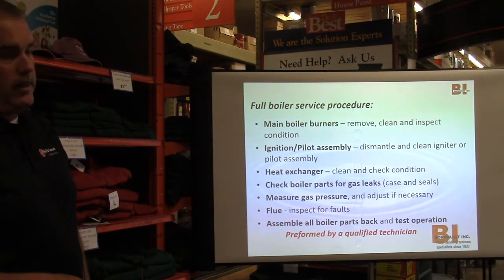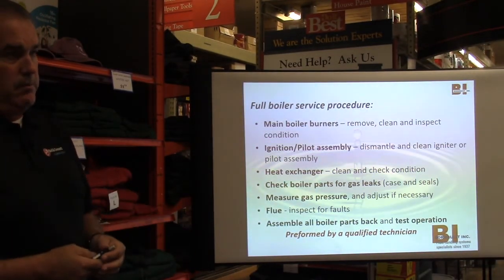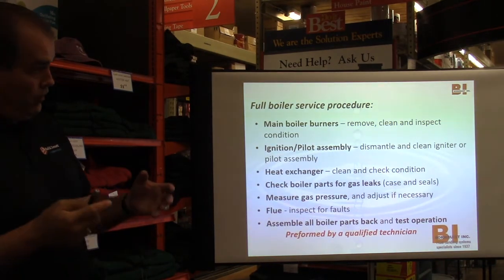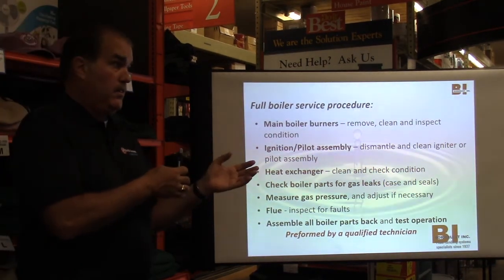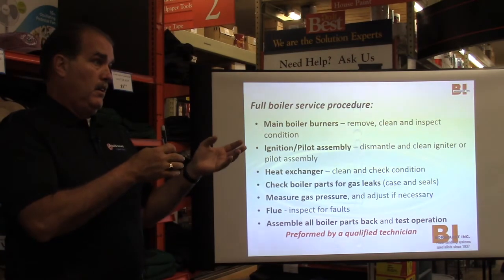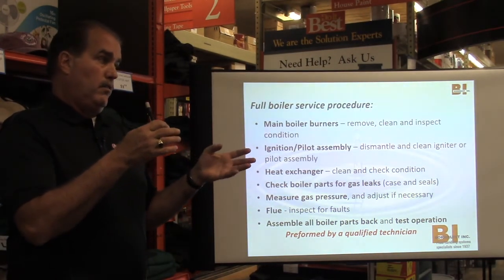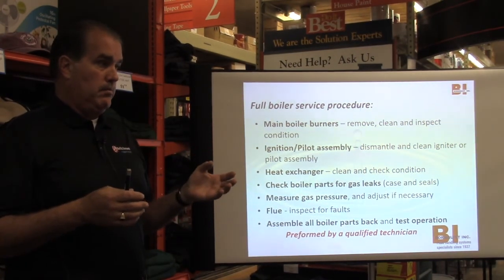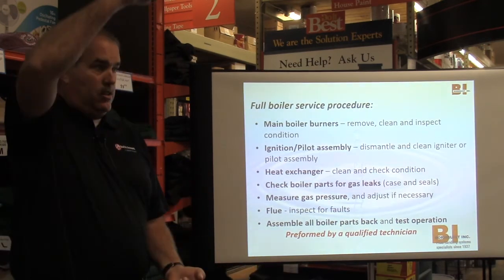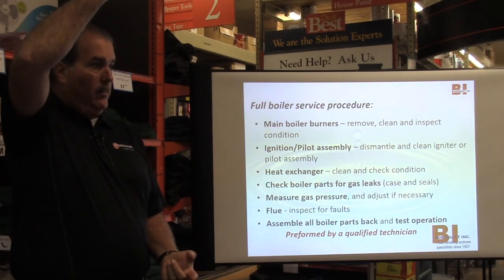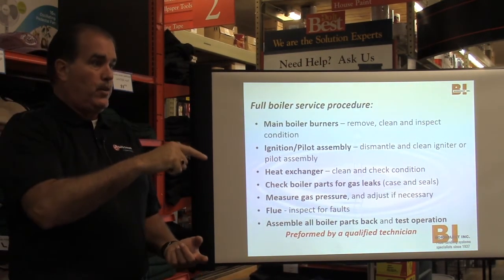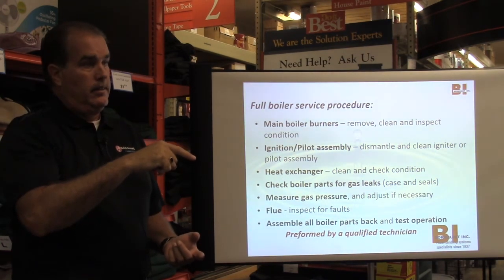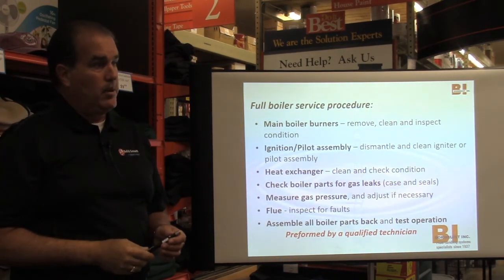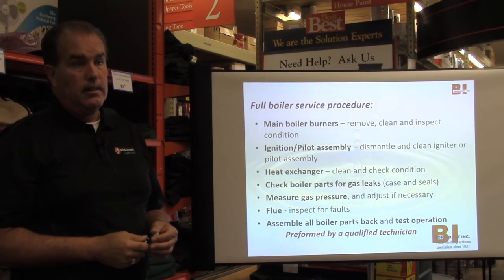So you want to make sure you've got the right amount of gas pressure coming into your building. You also want to check for too much. A manometer reads in inches of water column, and 28 inches of water column is 1 pound. They run around 14 inches as a high end. So that's a half a pound of pressure. That's not a lot, but you need that.